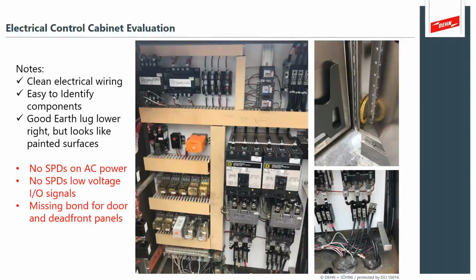Here's a nice cabinet, but in all of its nice workmanship and good clean arrangement, what is not obvious is that there's no SPDs on the AC power protection. There's no SPDs on the low voltage data signal applications. There's missing a bond on the front door. Now that sounds subtle and like, well, that's no big deal. That stuff is a contributor to other noise issues. And you'll see other examples where we can show that dead front should be dedicated bonded.